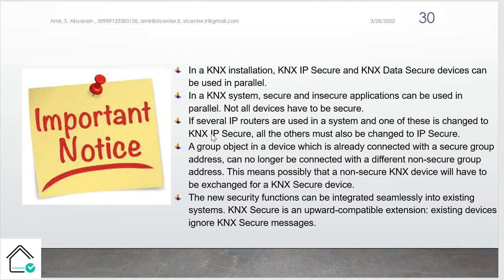In a KNX installation, KNX IP Secure and KNX Data Secure devices can be used in parallel. It is possible to have some devices with KNX Secure and some devices non-secure. In a KNX system, secure and insecure applications can be used in parallel. Not all devices have to be secure. If several IP routers are used in a system and one of these is changed to KNX IP Secure, all the other routers must also be changed to IP Secure. It means, because you want to have the data broadcast between the routers, you cannot have one with secure and the rest non-secure and have secure communication. Of course it works, but it would be non-secure.